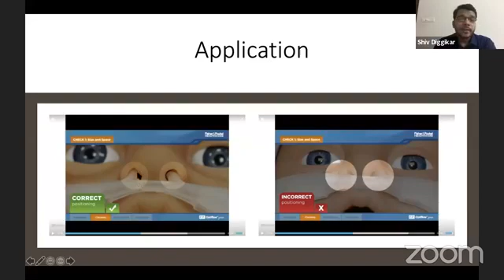First of all, the prong should never cover more than 80% of the nasal orifice. Okay, cannula to nare ratio should never exceed 80%, and most of the time it is around 50%. The prong should never ever cover beyond 80%. That's the maximum recommended. Never close the mouth while giving HFNC, because the amount of pressure generated, the CPAP generated, is very variable. Should never close the mouth while giving HFNC.